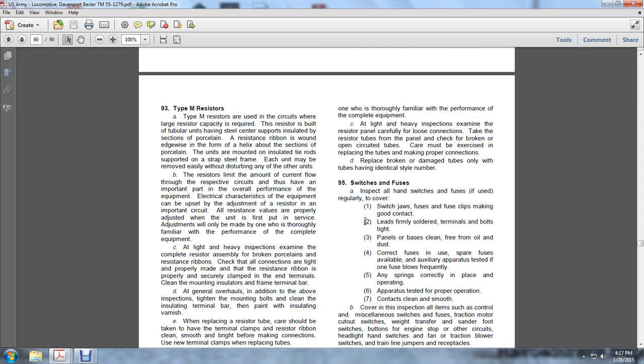At light and heavy inspections, examine the resistor panel carefully for loose connections. Take the resistor tubes off the panel and check them for a broken or open circuit. The tubes should be checked, and the most careful attention must be exercised in replacing the tubes and making proper connections. Replace broken or damaged tubes only with an identical style number.